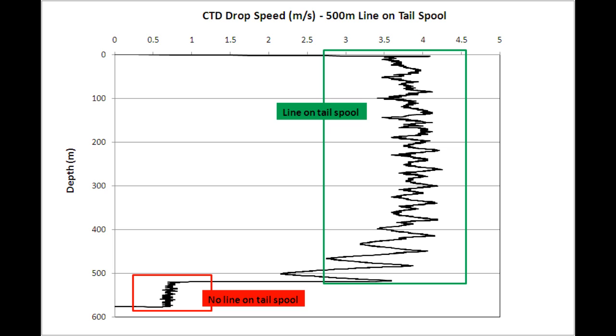The current CTD and SV software allows instantaneous plotting of the probe drop rates when the data is downloaded, and the reason for that is the drop speed is quite an important parameter to keep an eye on. What you need to do is make sure that the variation in drop rate doesn't increase much more than you see on the chart here. Certainly the lowest drop speed with line on the tail spool shouldn't be much less than about 2 meters per second.